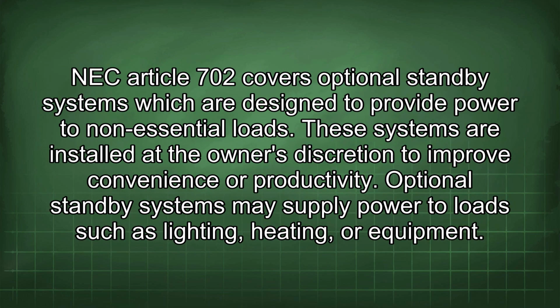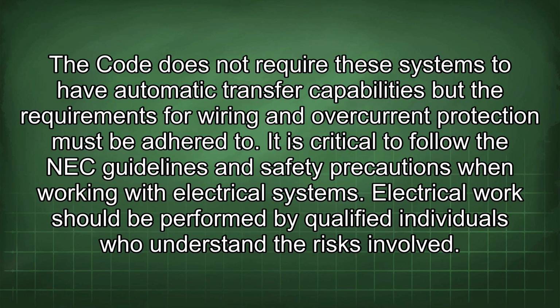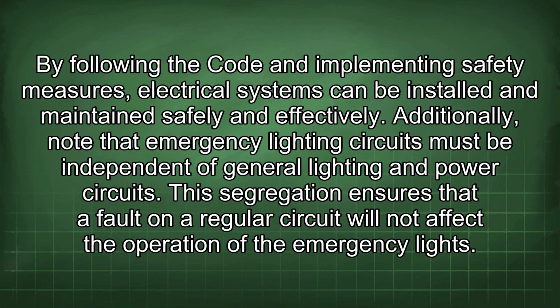NEC Article 702 covers optional standby systems which are designed to provide power to non-essential loads. These systems are installed at the owner's discretion to improve convenience or productivity. Optional standby systems may supply power to loads such as lighting, heating, or equipment. The code does not require these systems to have automatic transfer capabilities, but the requirements for wiring and overcurrent protection must be adhered to. It is critical to follow the NEC guidelines and safety precautions when working with electrical systems. Electrical work should be performed by qualified individuals who understand the risks involved. By following the code and implementing safety measures, electrical systems can be installed and maintained safely and effectively.